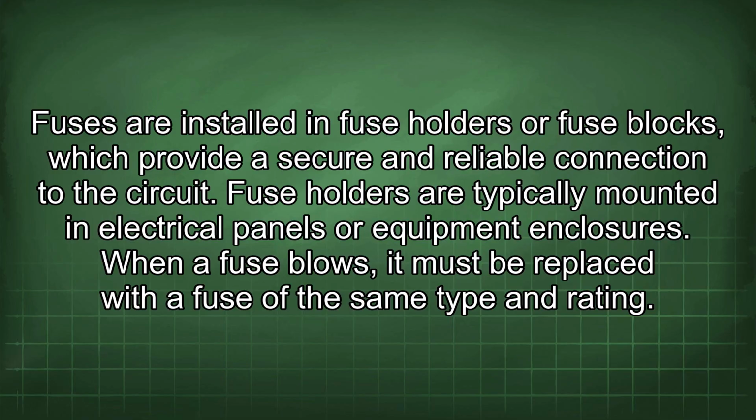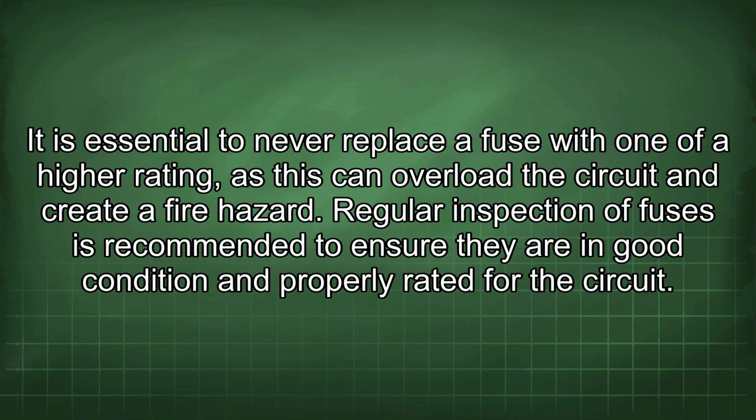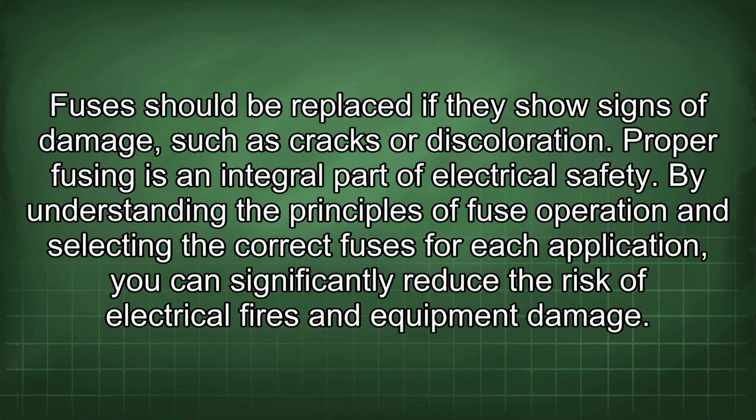When a fuse blows, it must be replaced with a fuse of the same type and rating. It is essential to never replace a fuse with one of a higher rating, as this can overload the circuit and create a fire hazard. Regular inspection of fuses is recommended to ensure they are in good condition and properly rated for the circuit. Fuses should be replaced if they show signs of damage such as cracks or discoloration.